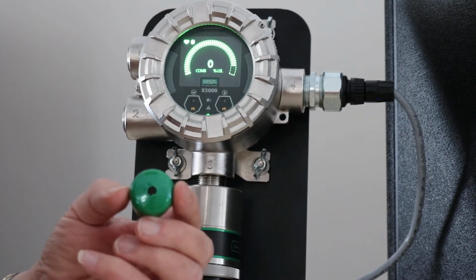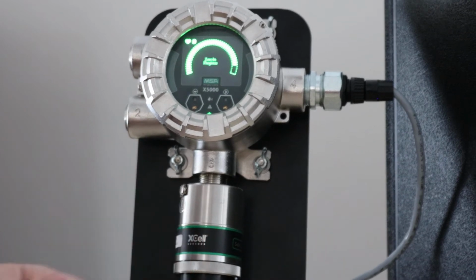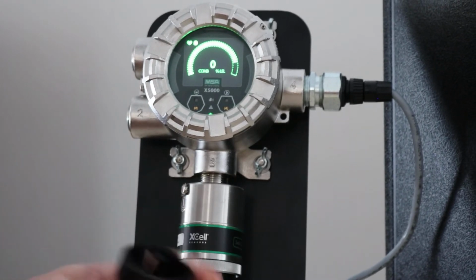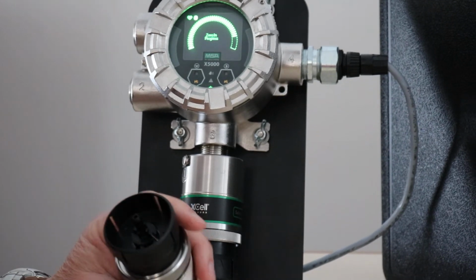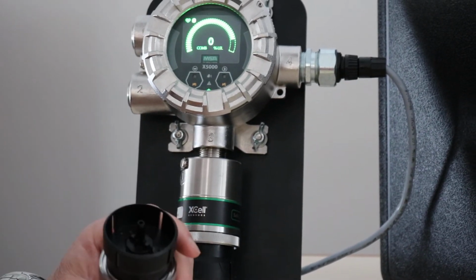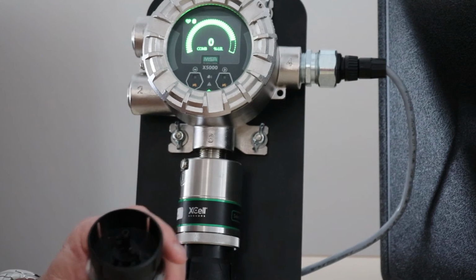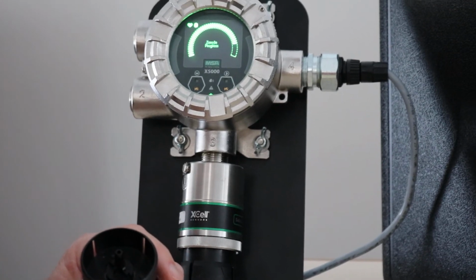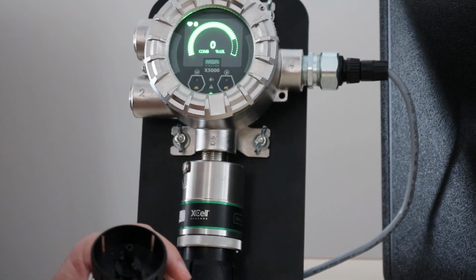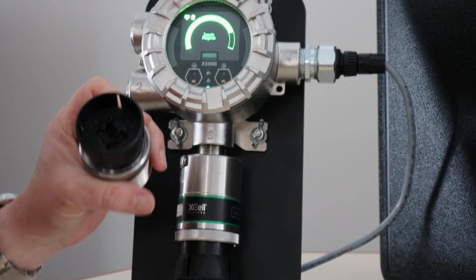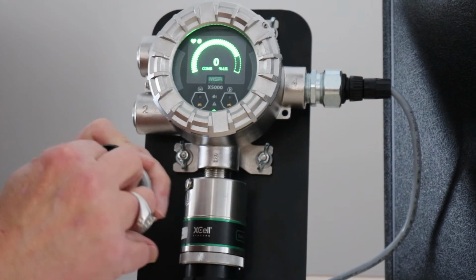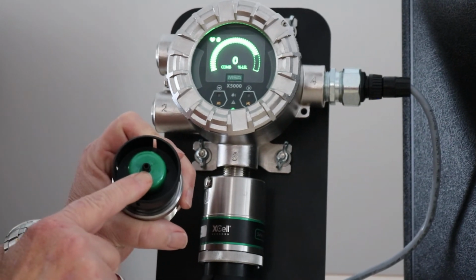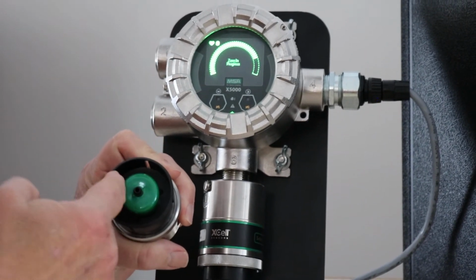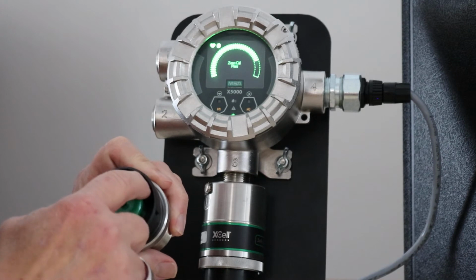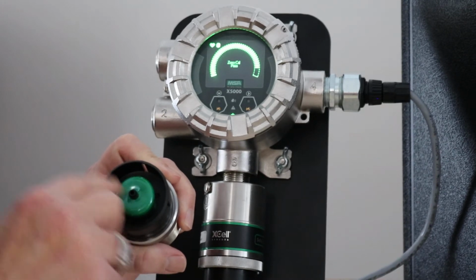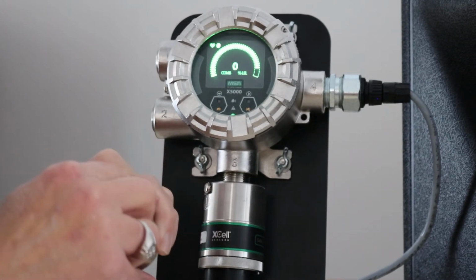This little green cap, which you will find in the calibration kit, is used for the sensor in a high ventilation or high wind area. If your unit is outside or in a room that is high ventilation, then you want to put this little cap on, and then your calibration tubing goes here, and what this does is it blocks the wind from blowing the gas out of the sensor while you're doing your calibrations.